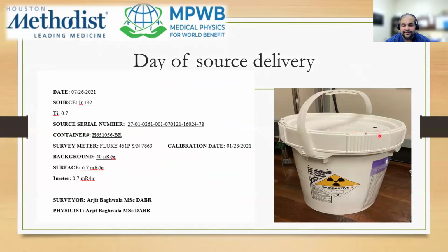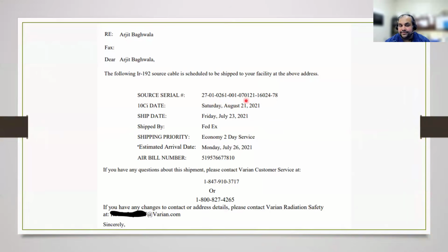The source is typically delivered in a bucket. It looks something like this, and as soon as you receive it, within 3 hours of delivery, it is recommended for the physicist to do a survey of the bucket. Because the source is not in liquid form and is sealed and encapsulated, you don't necessarily have to do a leak test. I know, like in our clinic, we do it. Also, it gives our residents a practice of going through the steps, but yeah, you do have to get your surface readings and your readings at 1 meter. The bucket will have the delivery papers with the source serial number that you as the physicist should check with the email that was sent to you. So over here you can see those are the papers, and as soon as you take it out, you should compare the source serial number with the letter that you received a couple days prior to the delivery of the source.